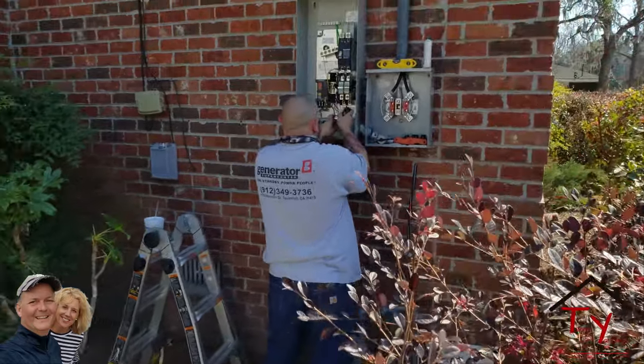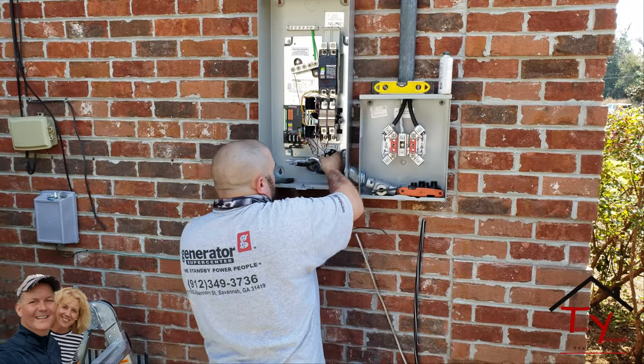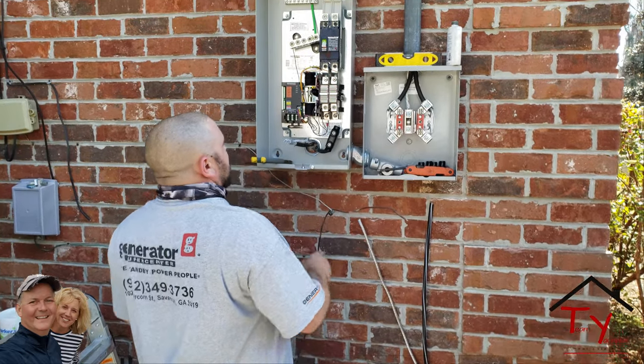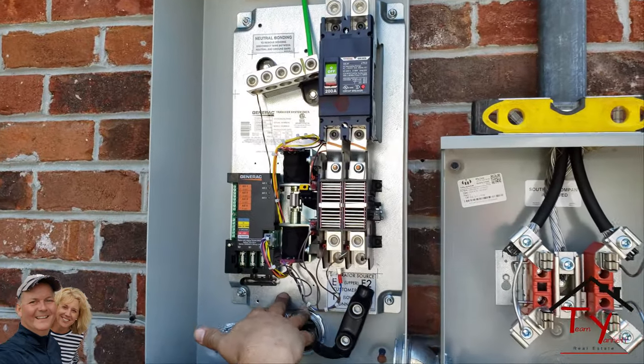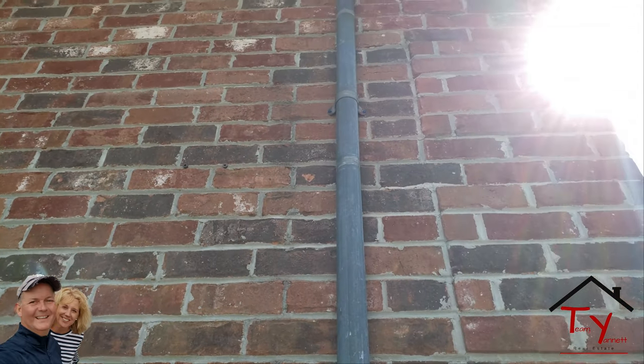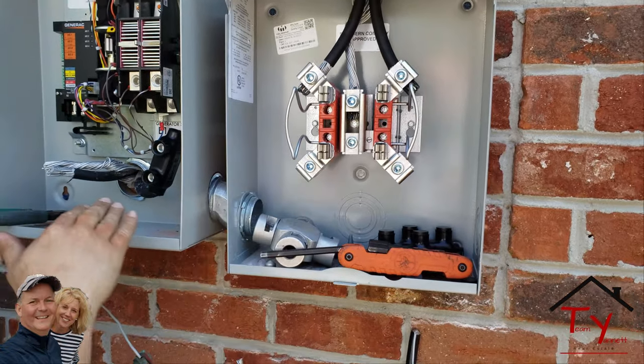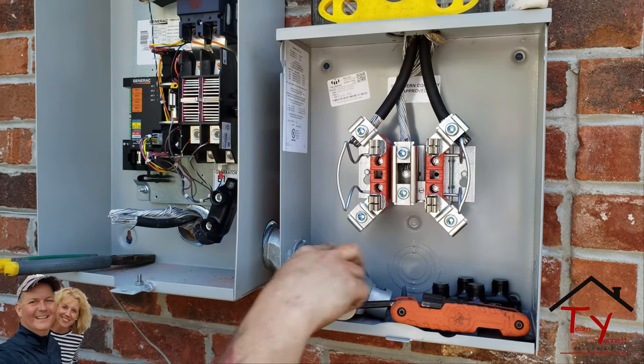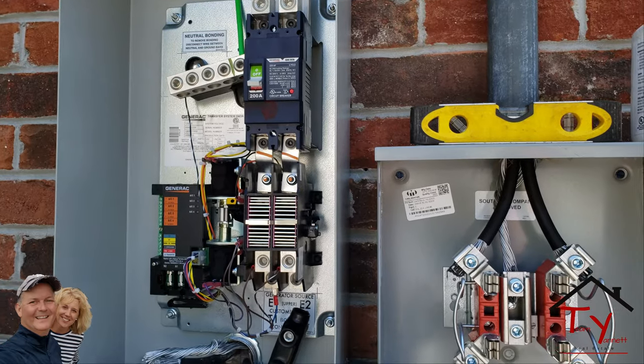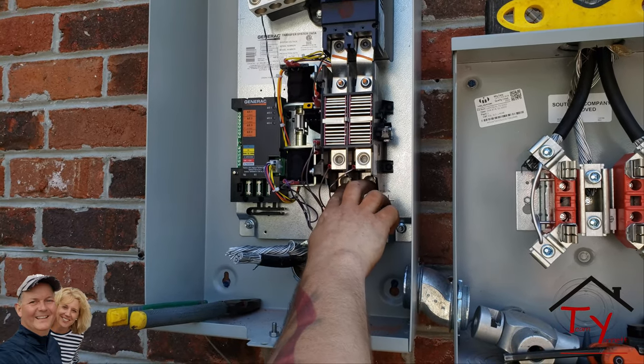And it's perfect because I can see the gas — and I'm assuming it's gas, right? That's correct. This machine is a dual fuel machine, so it can be run on either natural gas or liquid propane. The gas meter is right there and the electrical meter is right there — this couldn't be any more perfect. Most of our turnkey installations come with the first 20 feet of electrical footage and the first 20 feet of natural gas or propane footage. These are Polaris connectors — this is what actually connects the ATS to go into the power in the home. The weather head comes through the meter, but instead of going from the meter directly into the home, it goes from the meter to the top of the ATS, which is your main disconnect for the home.